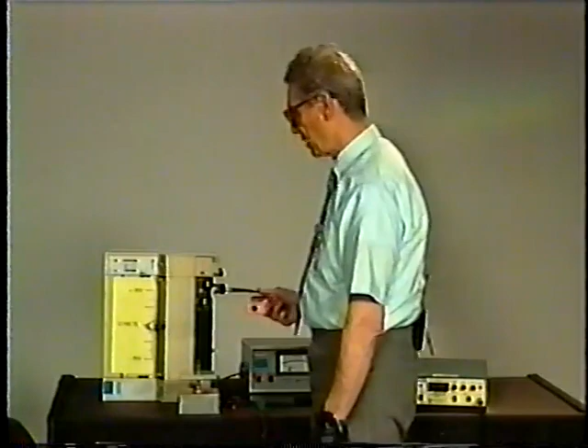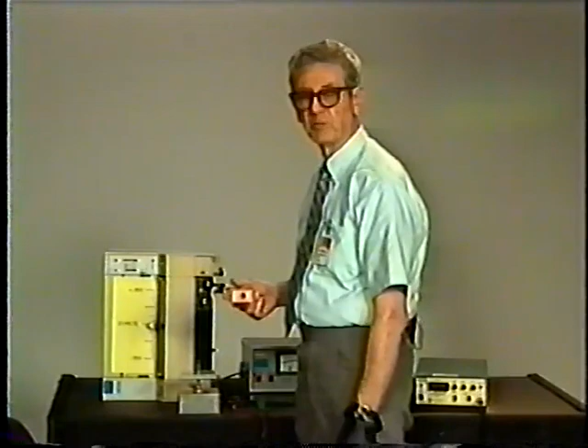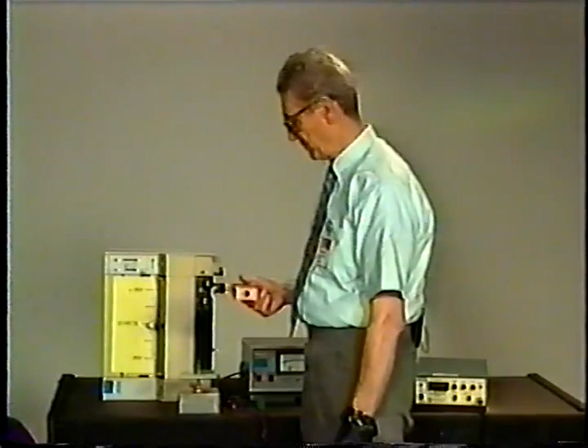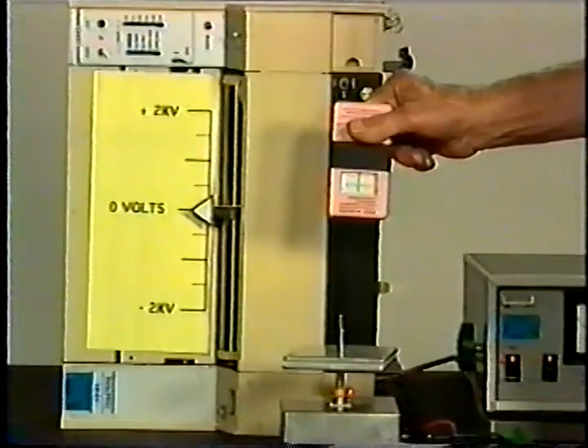At Lockheed Martin, we use this electrometer system to measure the charge at the workstation to determine if there's any potential for damaging sensitive electronics. We do not use handheld field meters to survey insulators and other objects in the area. To demonstrate the unreliability of the reading that you get from one of these meters, the setup here has a Teflon surface that has a plate sitting on top of it, and everything is at zero. The meter is reading at zero.